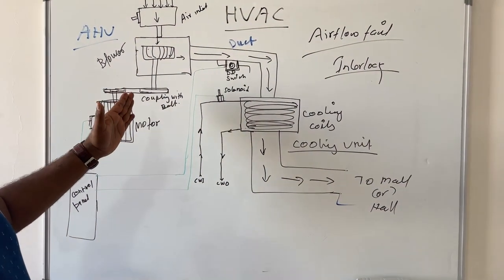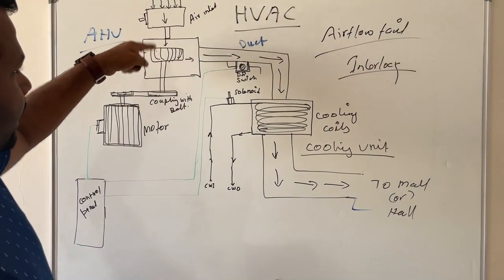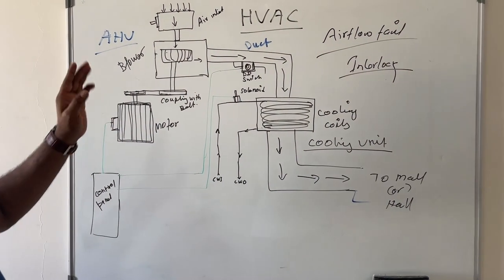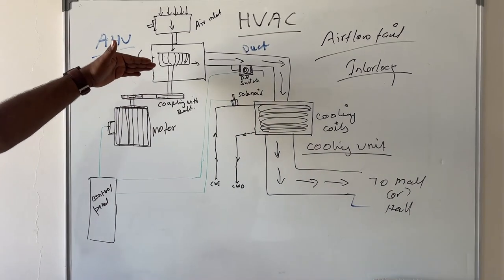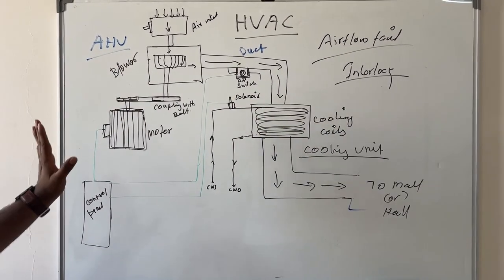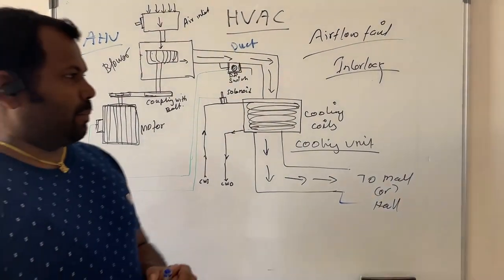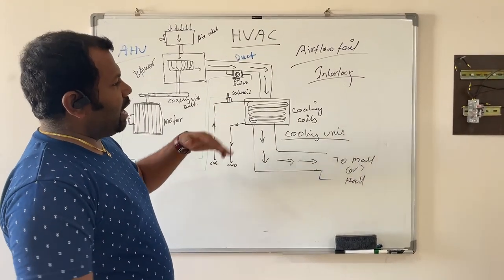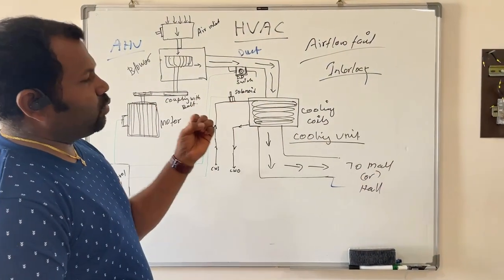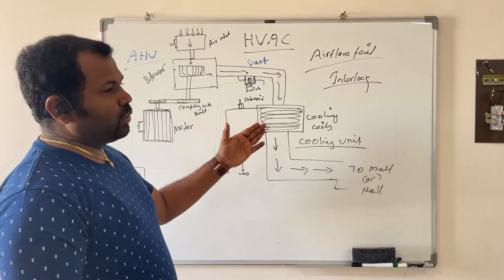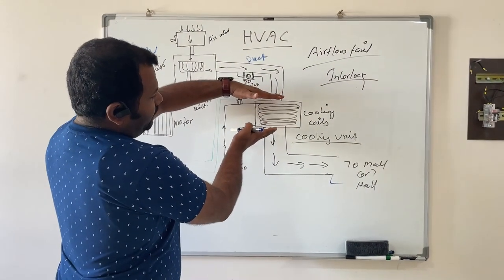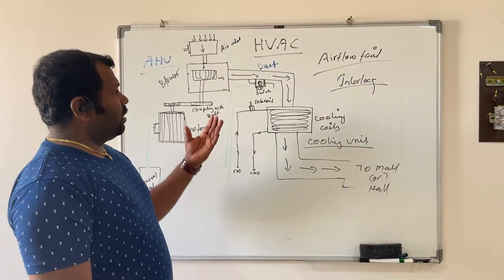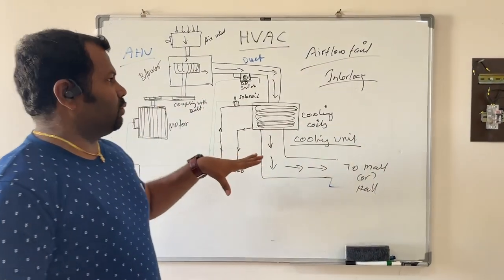The blower is working through the electric motor, sucking air from outside and passing it through the cooling coil. Now if this belt is cut or due to any mechanical reason it is broken, air is not flowing. Still the cooling coils will be cooled by the cooling gas or water, and after a certain time, since air is not passing through, ice will form in this cooling system.